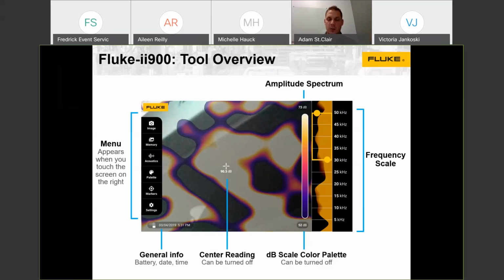But the ultrasounds that we can't hear with our ears can also be visualized by the II-900, up north of 15, up into that 50 or 52 kilohertz range. And so the yellow box that you see on the screen there is adjustable, both how wide that range is and the center of the range that you're looking at. And why that's powerful is because it helps you in really noisy environments to eliminate all that sound that we hear with our ears and focus in on the sounds of a vacuum leak or the sounds of a compressed air or gas leak and eliminate all of the noise.